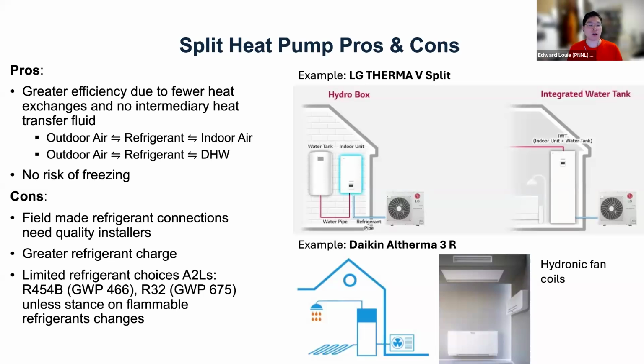Even glycol, if you mix glycol at 10% and stuff like that, there is a temperature at which that 10% glycol mix will freeze. But with refrigerants, the freezing point is so low that you don't have to worry about it. But one of the cons of these types of systems is that because it's refrigerant going inside the building, the number of approved refrigerants that can go inside the building, especially with the refrigerant GWP step down, is quite limited. Like right now, R454B and R32 are the two refrigerants that are going to be replacements for R410A that can still go inside buildings. So more limited refrigerant choices.